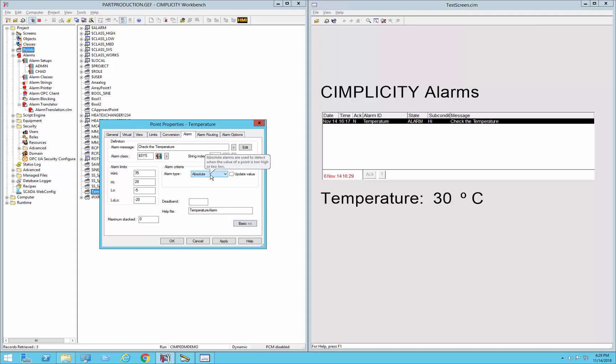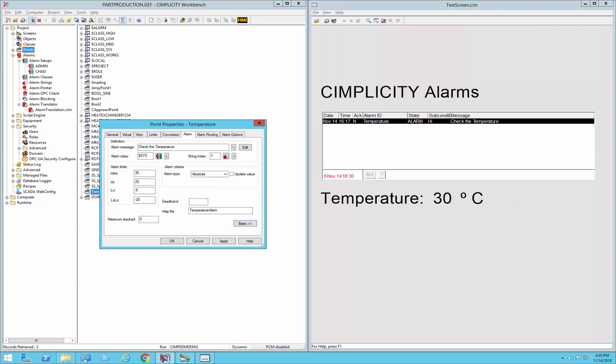So we talked about absolute alarms in the initial demonstration, which basically alarms a point whenever it is outside or above or below these ranges. So you can see in the runtime that we have our alarm currently in a high alarm state because it's above 28 and below 35. So that is your absolute alarm limits that it checks to see if it's within those ranges.